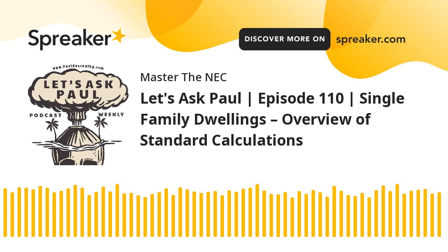All still applicable. Now, where it starts to get different is now when you're moving into the appliances. The appliances, it's the same thing. You still get to apply the 75% if you have 4 or more of the appliances, but you don't use the loads that are 240 volt, only the loads that incorporate a neutral conductor.